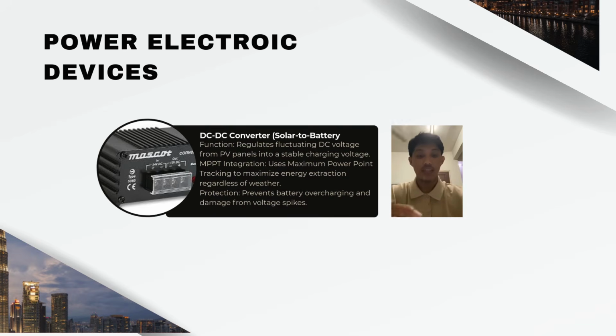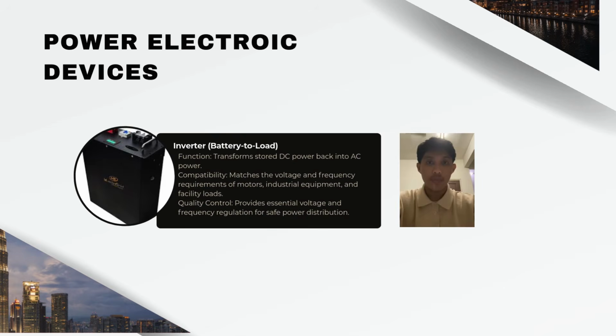This technology harnesses the best possible power extraction from the panels while regulating the voltage to a level safe for the battery. This protects the system from overcharging and significantly extends the battery's lifespan. The last device is the inverter. The inverter is the gateway to our distribution panel. Since industrial equipment, motors, and facility loads run on AC power at specific voltage and frequencies, the inverter converts our stored DC energy back into high quality AC.